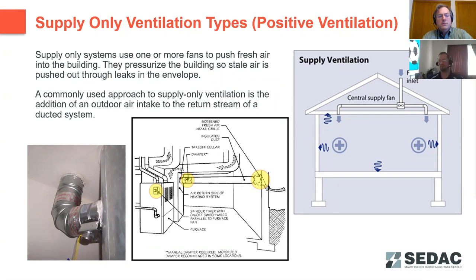Because especially in mild weather, your furnace fan isn't normally going to run enough to draw in that ventilation air into your building. So to meet the required ventilation air change rates for fresh air, there's usually a timer added on to your furnace. You can see in the middle picture, it's highlighted there on the furnace, that opens a damper and kicks on the fan to bring in that fresh ventilation air, even if there isn't a demand for that unit to run for space conditioning purposes. And so that's probably why this one isn't as common. There is that additional design complexity in supplying that fresh ventilation air.